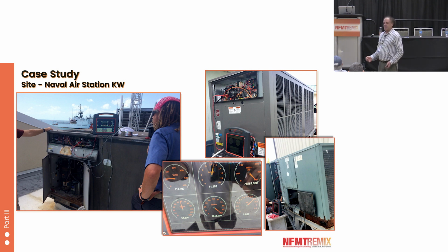First we did a baseline measurement where they measured the efficiency, power consumption, and the cooling capacity of the unit, and then they did the service actions that would target the issues that were uncovered. I mean, a simple example would be if it needed more refrigerant, we add refrigerant charge. Or if the TXV needed adjustment, that was done.